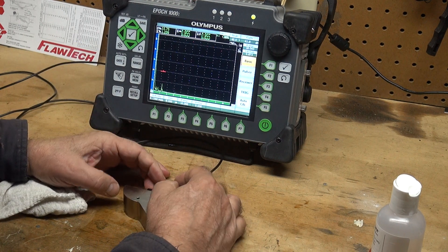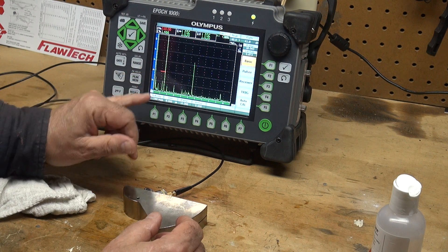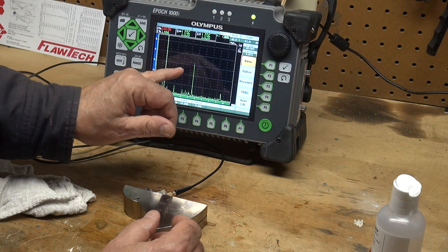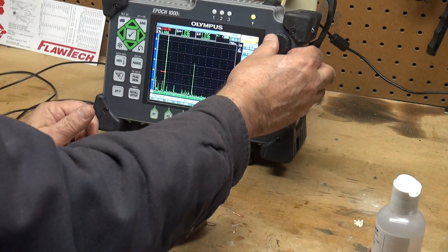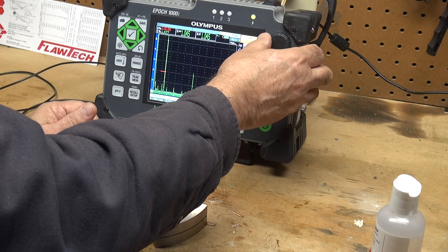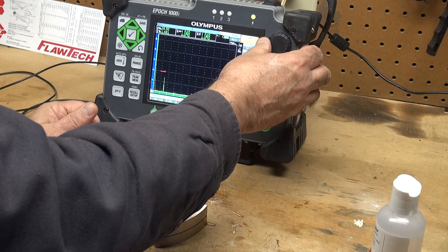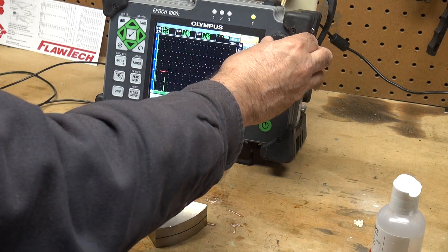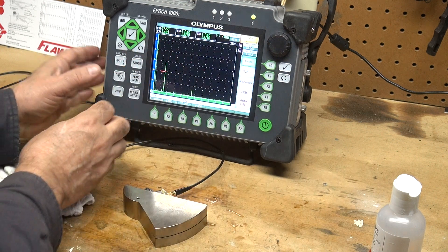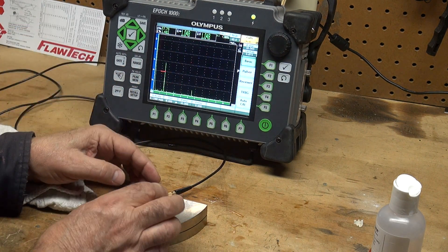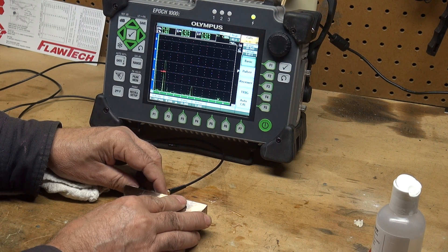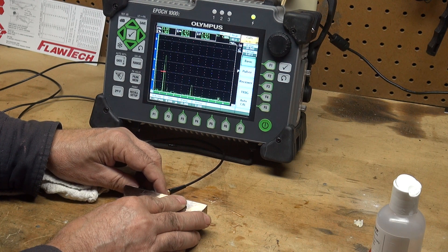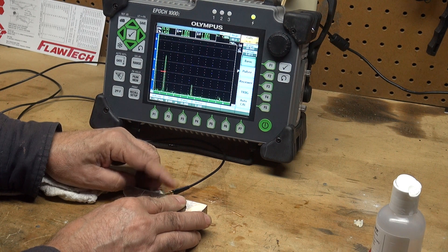So I'm going to put the transducer on and I can see three reflectors. I know that's a one-inch reflector, this one here is a five-inch, and that's a nine-inch. Let me take down my gain a little bit so I can see that one-inch radius at a little bit easier angle to work with. Now let's hit peak memory and I'm going to move my transducer back and forth again to establish my beam index point.